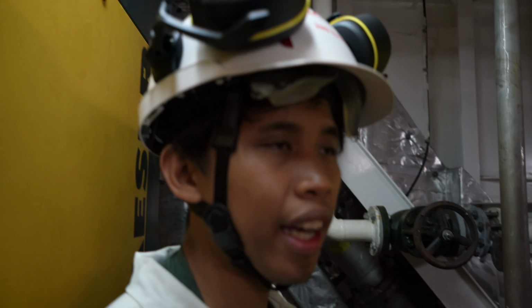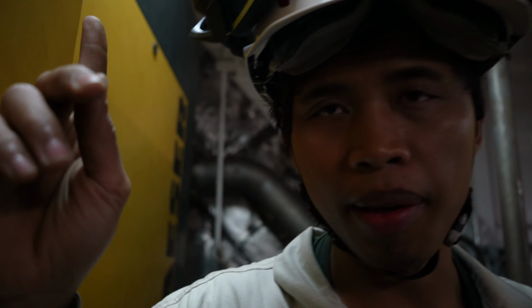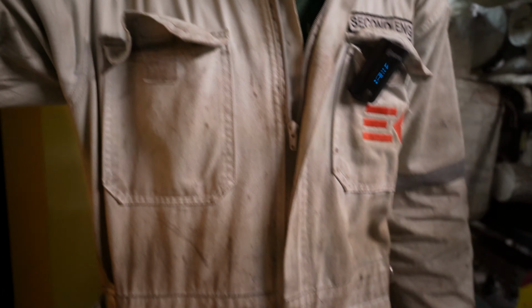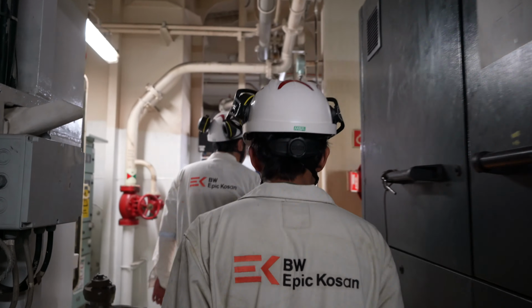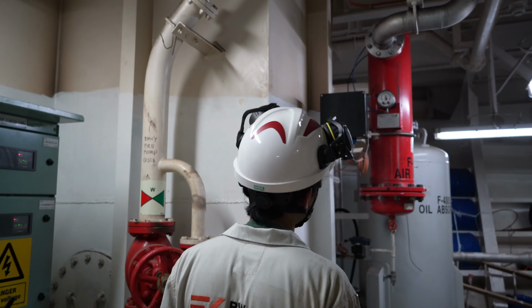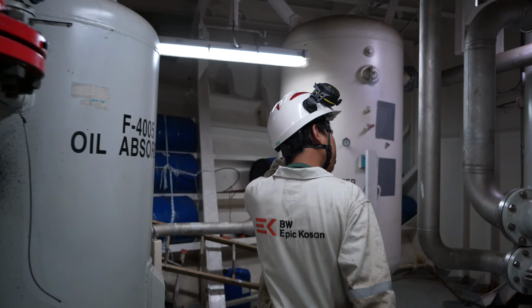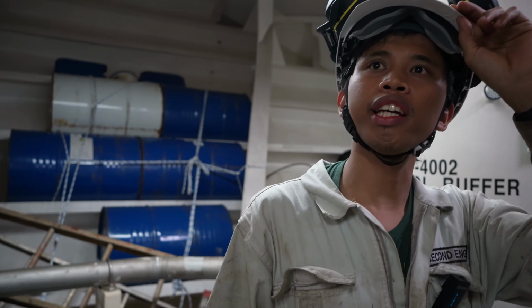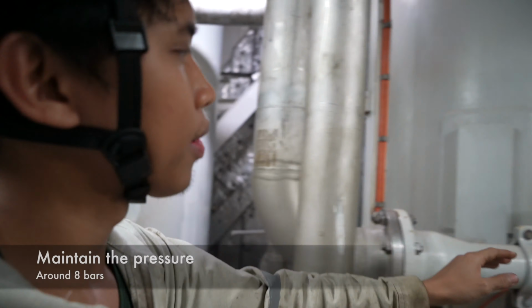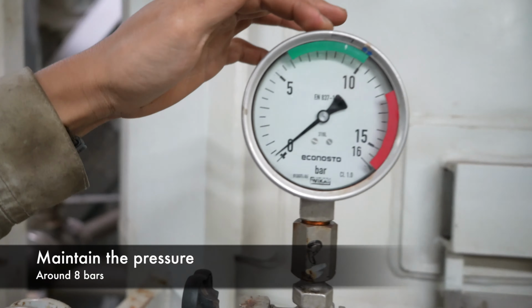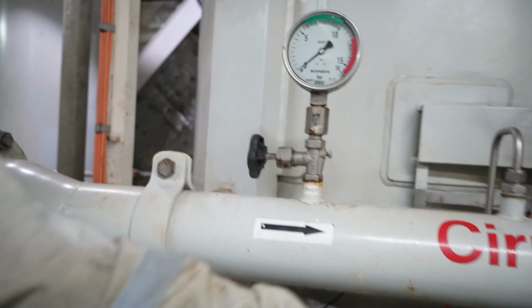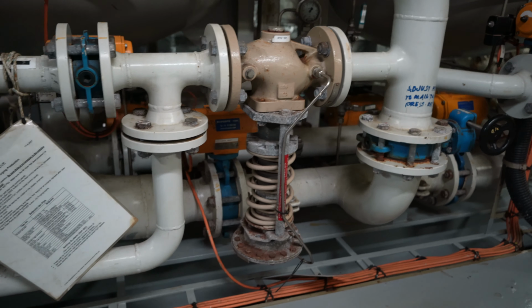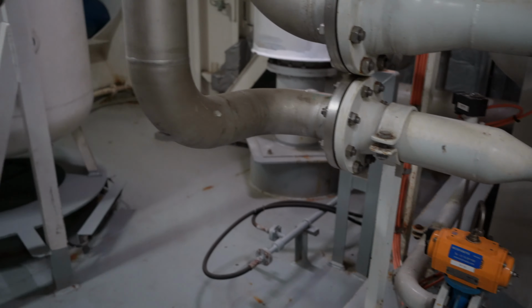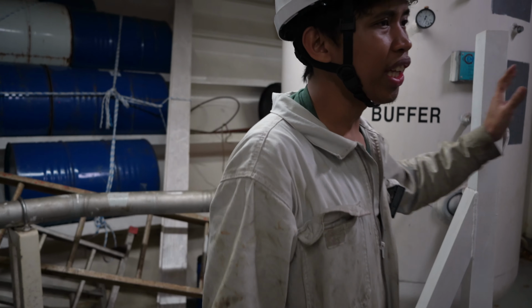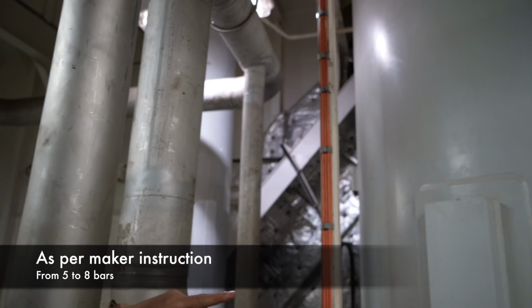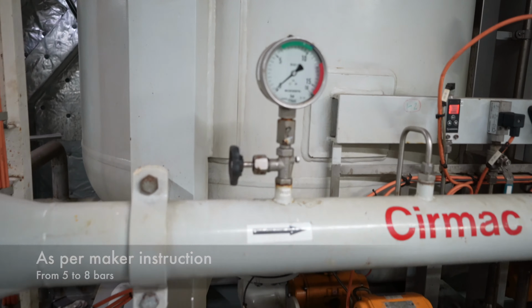Once we have pressure and the air dryer is running, we can proceed to the PSA. We have pressure and we have the dryer running. Here we have to maintain 8 bars. Going to the PSA, all the valves are closed, and then we have to stabilize the pressure in the system first. We have the buffer tank, and then we have the inlet pressure. It needs to be at least 8 bars.